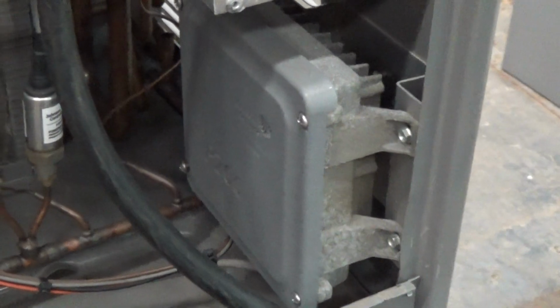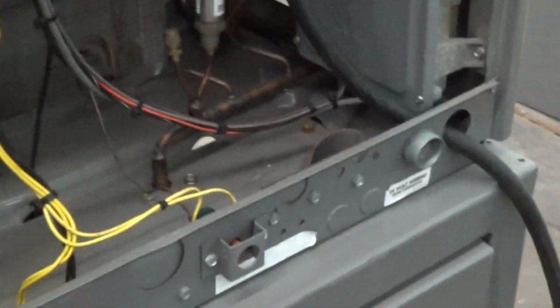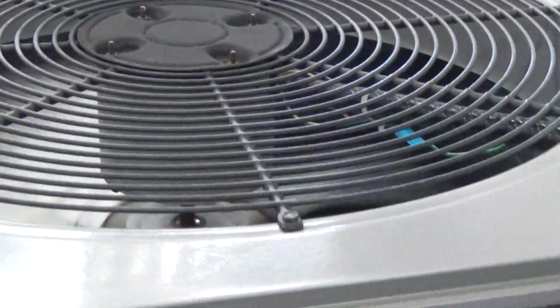We have all the covers on the unit, the lid, side covers. We touched up a little bit of paint. This here is the low ambient fan speed control, which allows this unit to be run outside. On a chiller like this, the fan does not always have to be running when the compressor is running. Get our ladder here. For example, right now it's just running at a very slow speed based on the conditions that are in the shop.